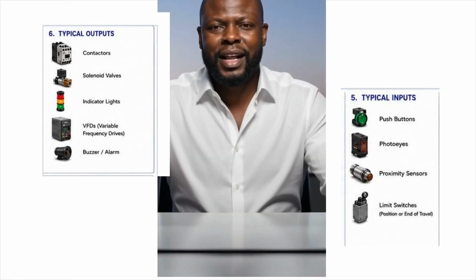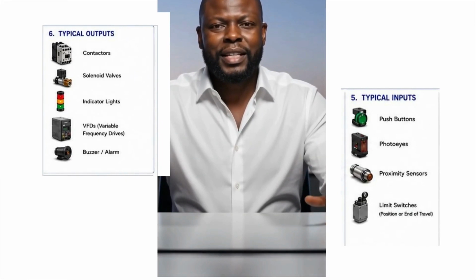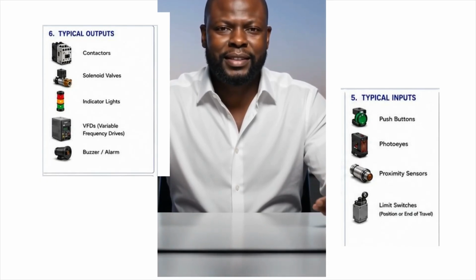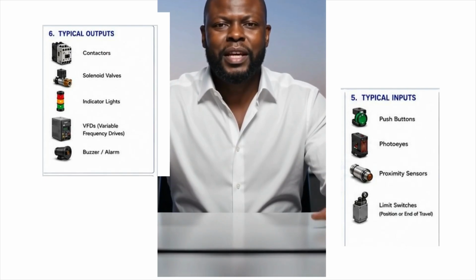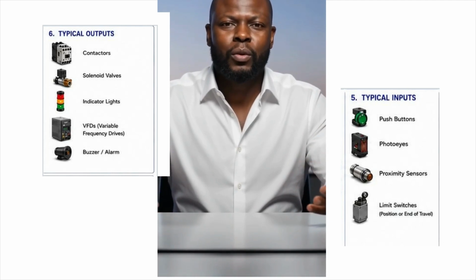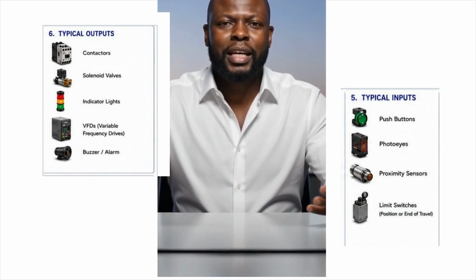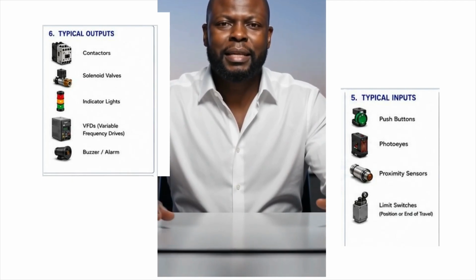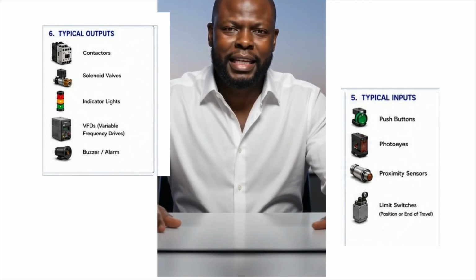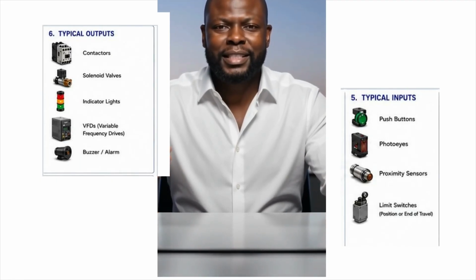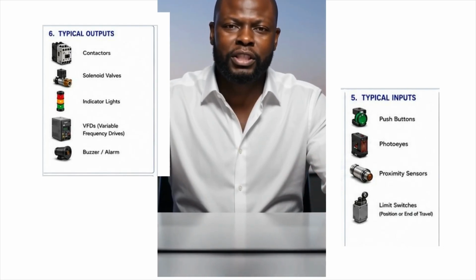Now here's something worth internalizing early before we go any further. Experienced technicians rarely blame the PLC first. When a machine stops, the PLC is usually not what actually failed. Before you ever replace one, walk it in order: sensor, wiring, the 24-volt supply, the PLC's input LEDs, the output LEDs, and only after all of that checks out does the CPU itself become a suspect. That order matters. It goes from most likely to least likely. Field devices, wiring, and power supplies fail way more often than the PLC's own logic does.